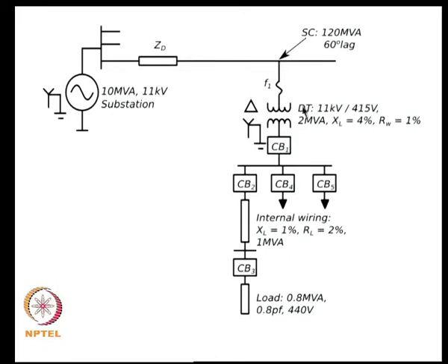In this case, a fairly large facility is being connected to the feeder, and you want to look at what should be the rating of the fuse and circuit breakers coming back in from the facility. In the last class, we looked at what is the impedance looking back from the point of common coupling, taking the feeder connection as the point of common coupling, to evaluate what would be the fault current that the fuse would see.